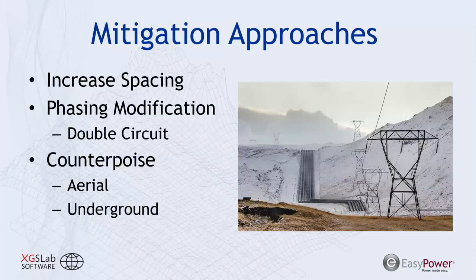Something that you can incorporate into the design or into a brownfield or an existing system is counterpoise. This can be a conductor that is either strung along the transmission line, much like a shield wire would work, or it can be buried between the recipient and the transmission line, and that would essentially have a current induced upon it that creates a magnetic field that reduces the end recipient's, your pipeline's or your railroad's, overall voltage.